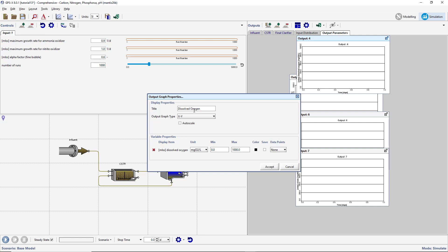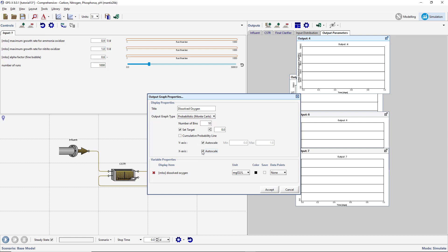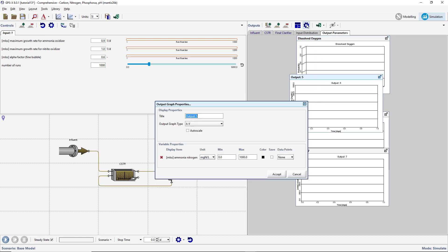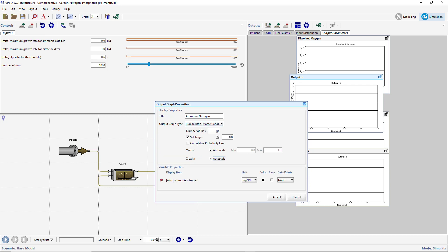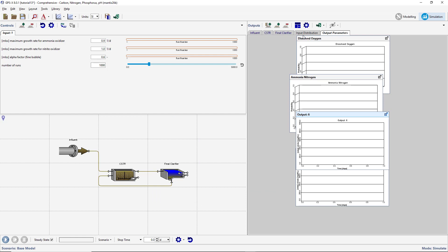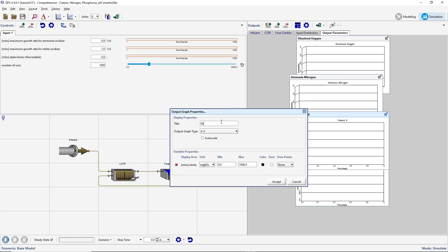When it comes to dissolved oxygen and ammonia nitrogen, we would like to view these graphs at a higher resolution and we would like to set an operational target. For the dissolved oxygen, set the number of bins to 20 to increase the resolution and set the target value to greater than 2 milligrams per liter. For ammonia nitrogen, increase the number of bins to 20 and set the target value to less than 3 milligrams per liter.